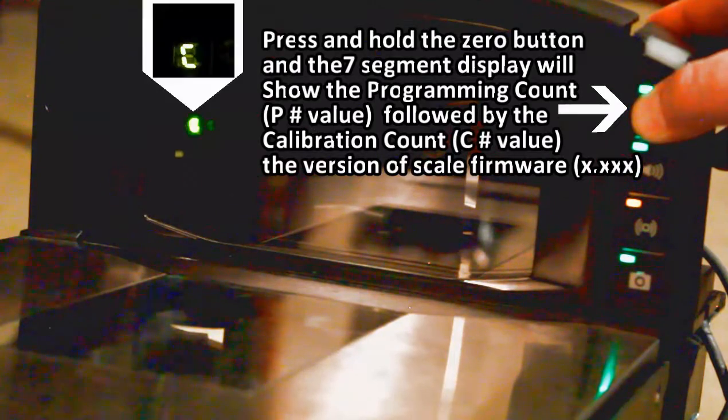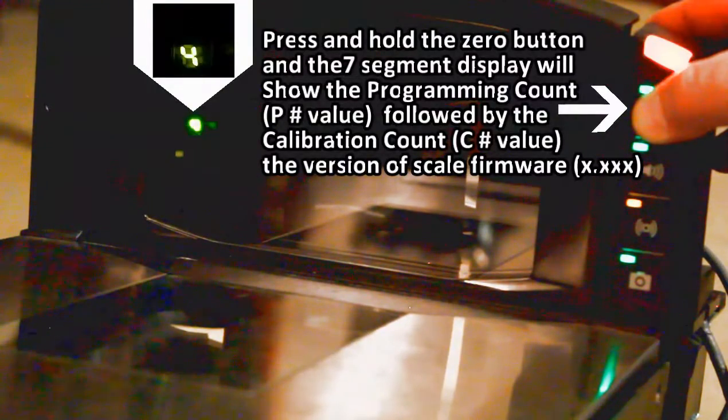To obtain the calibration count and programming count for the MP7000 scale for electronic sealing, since there's no wire seal on the device, you obtain these values by pressing and holding the zero button on the device. Then you observe the seven segment display window to capture those values.